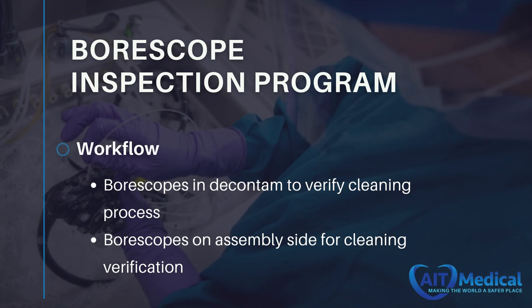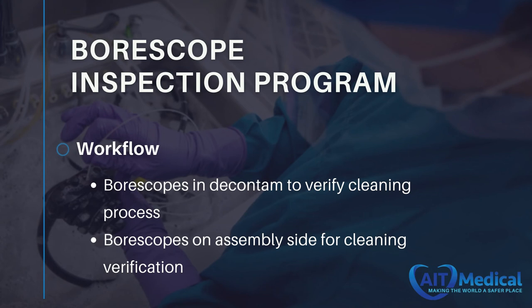While the focus has been on cleaning verification on the clean assembly side, it can also be useful to have a borescope available in the decontamination area for technicians to verify their own cleaning process. Pick a location that fits neatly into your workflow — avoid placing the borescope far from the assembly or cleaning area. In the endoscope cleaning area, the borescope should be positioned between the manual rinse step and the disinfection step or AERs, so the scope reprocessor can visually examine the scope after cleaning before initiating disinfection. For instruments, you will want the inspection scope at or near the instrument assembly stations and cleaning sinks.